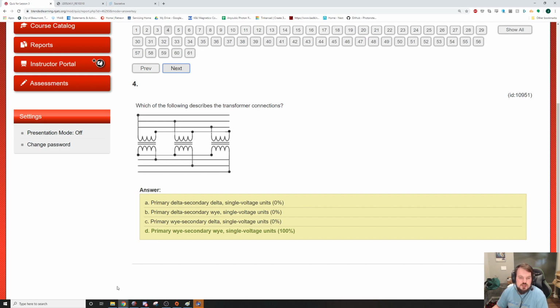Here you can see you've got 4 rows and 4 rows. This is a YY. So each one side of each coil is connected to A, B, C or L1, L2, L3. Then the other sides are all connected together. That is a Y.